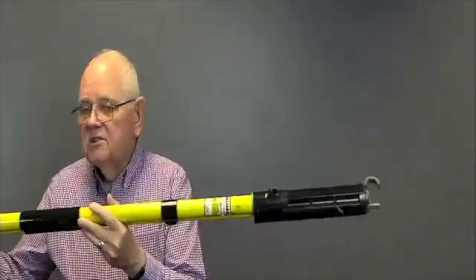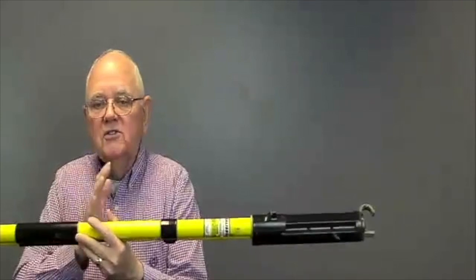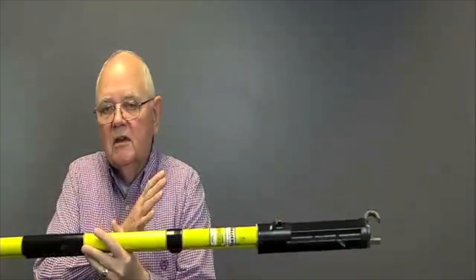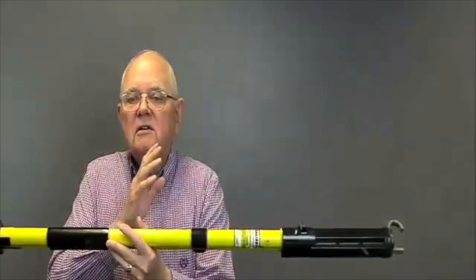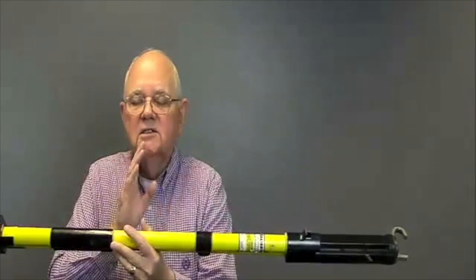Part of the lockout tagout process for medium voltages, we must install personal protective grounds. Now, all of these live line tools are insulated at 100,000 volts per foot. And then they get tested every 2 years at 75,000 volts per foot.